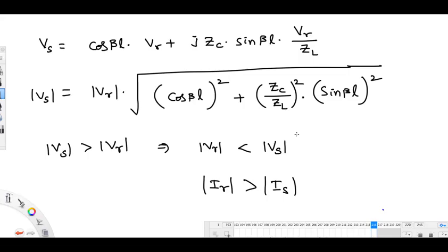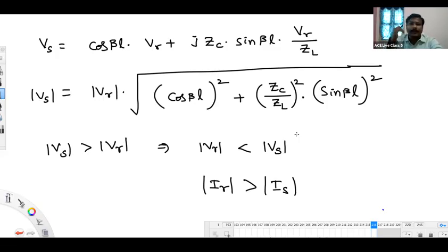So if you have decided some value of loading by taking this as a lossless line, by a tolerance you reduce the value. For example, you have decided to keep a load of 400 megawatt on a particular line by using this pure lossless line resistive analysis. Then if you go into a practical line, it's a lossy line and the load is not exactly equal to UPF. Then you have to take up that load less than 400 megawatt, maybe let's say 360 megawatt, 370 megawatt, like that they are going to limit.